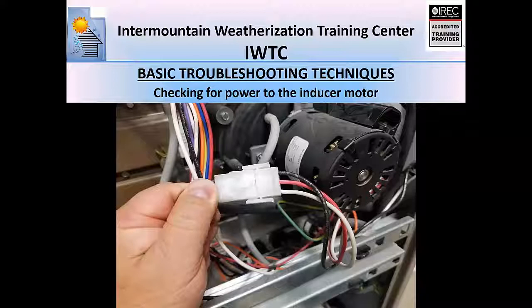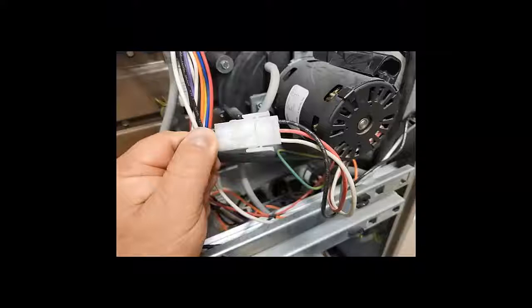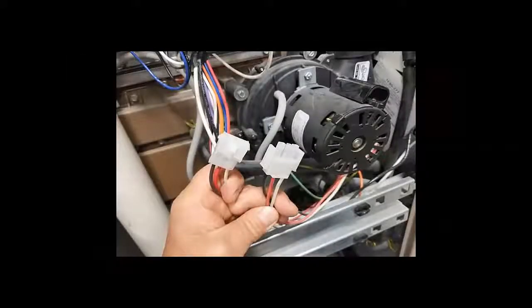So the next thing we'd want to look for is, do we have an inducer motor that's running? And here's a quick way to check power to the inducer motor. The next component in the basic sequence of operation is the inducer motor. If it is not getting the correct voltage or is defective, the furnace will not operate properly. Let's start by checking for correct voltage to the inducer motor. In order to do this, all you have to do is unhook the wires running to the inducer motor. In most cases, there will be a Molex plug you pull apart and check for correct line voltage at the plug. Always make certain the main power is off before disconnecting and reconnecting these wires.